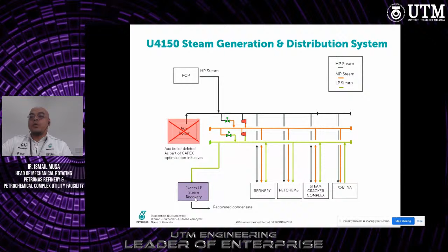So these are some of the process description on the steam distribution to users up to the battery limit. For generation, we have 3 levels of steam pressure. We have high pressure as the primary source from the cogen plant, and secondly medium pressure and low pressure from internal generation by process boilers and steam turbines. The balance of demand is handled via letdown stations. The distribution area is a centralized steam distribution from centralized utility facilities, through the steam letdown system to users.